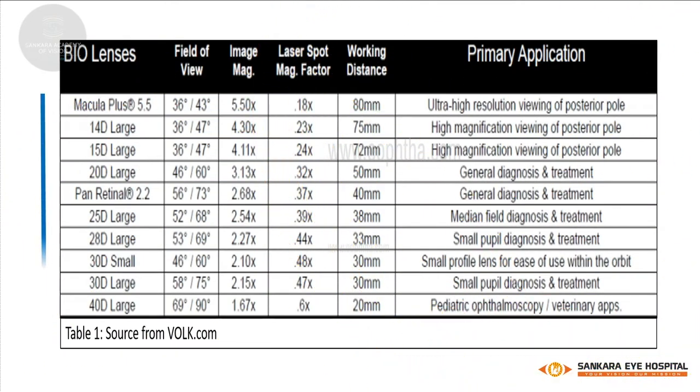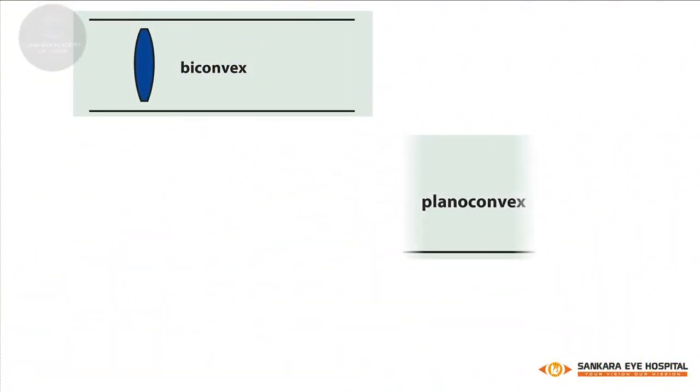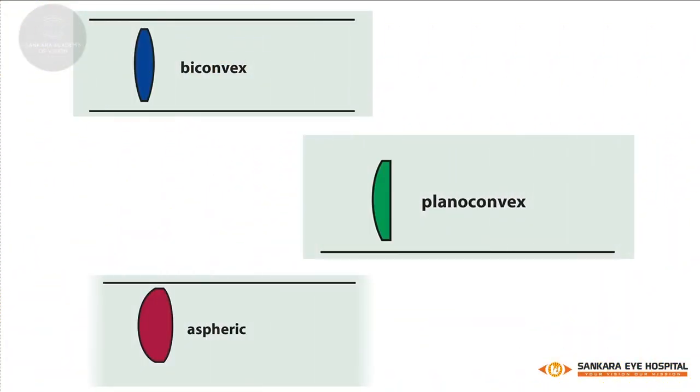As the power of the condensing lens increases, the field of view increases, but image magnification and working distance decrease. The surface of lenses could either be biconvex, planoconvex, or aspheric to avoid spherical aberrations during the examination.